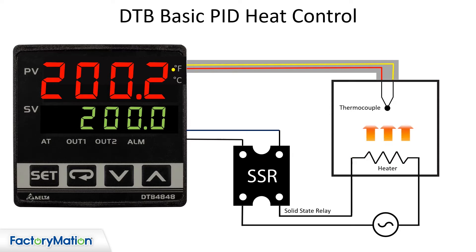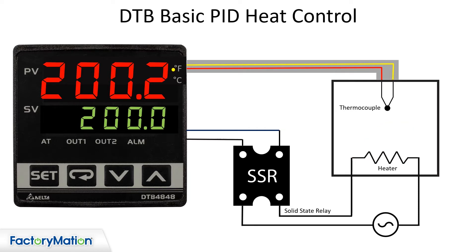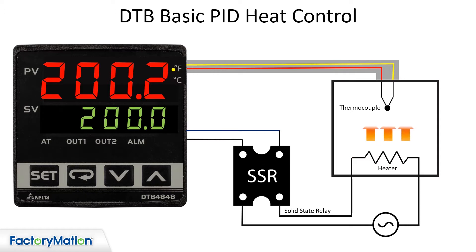A solid state relay is recommended due to the frequent on-off pulses the relay will receive from the DTB. The DTB uses PID calculations to determine the on-off ratio of the output in order to maintain a set temperature.